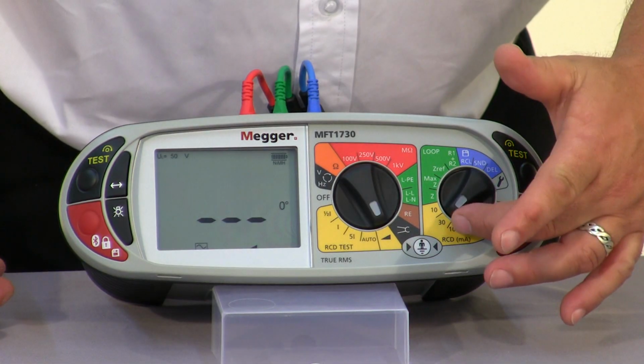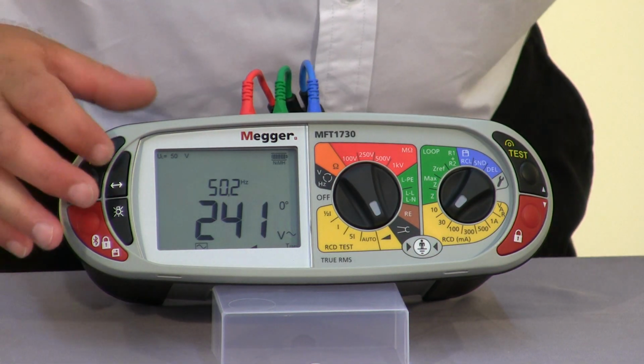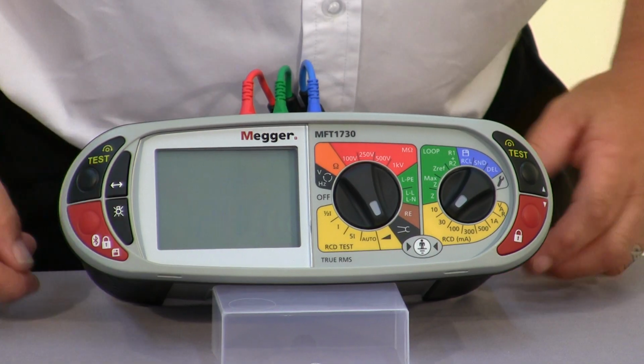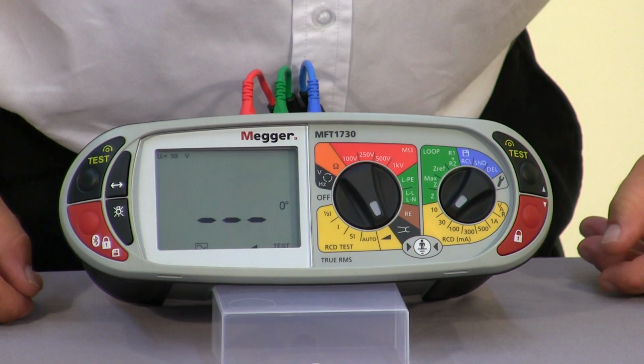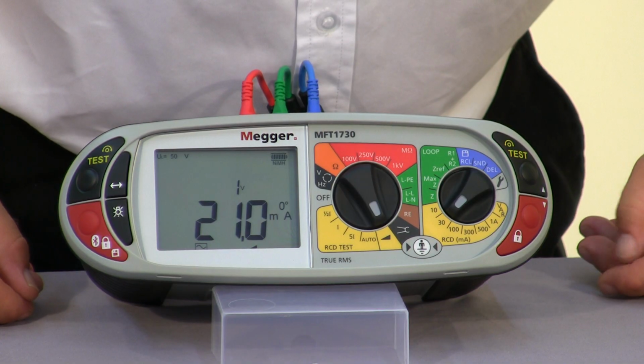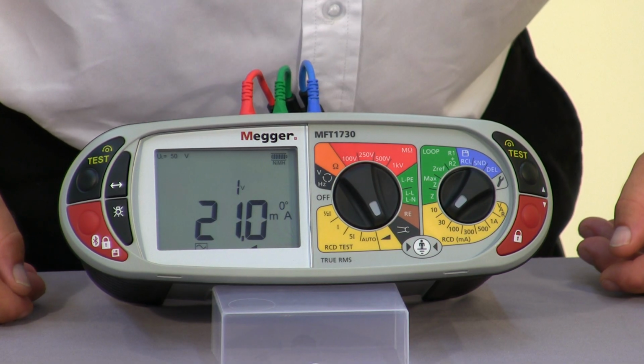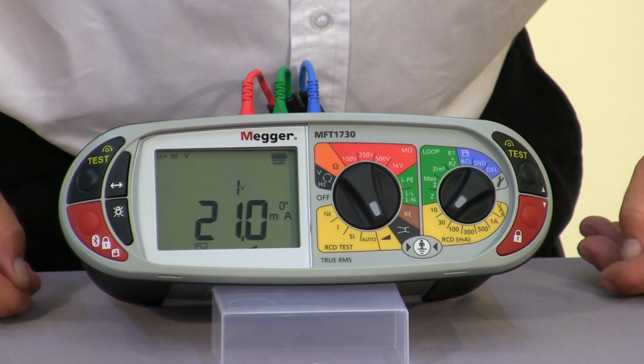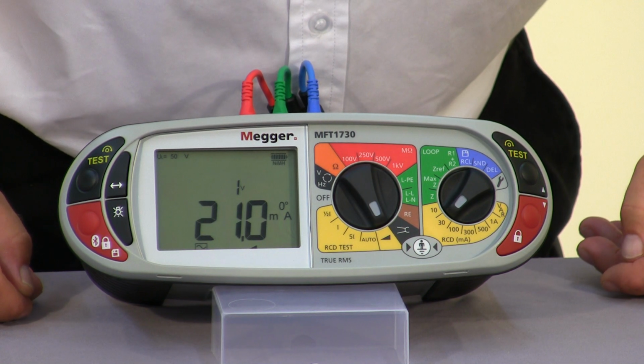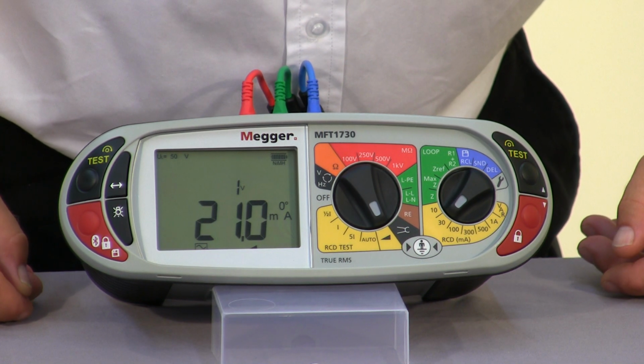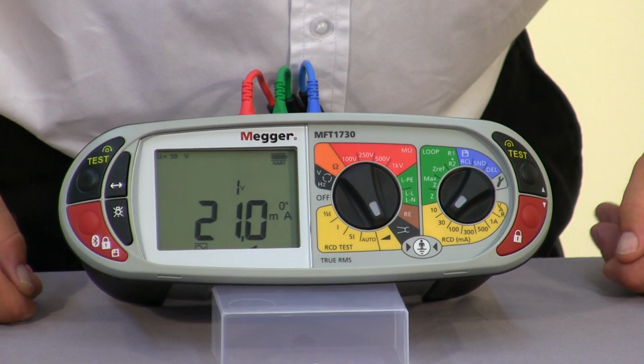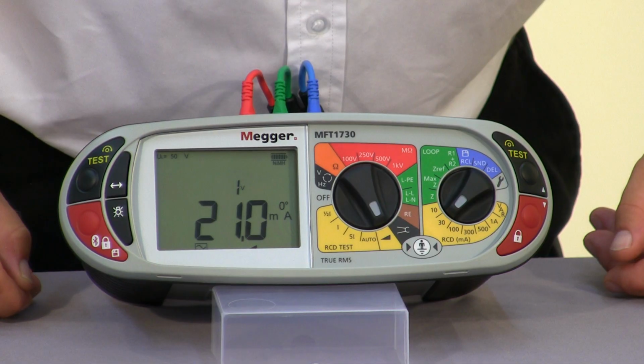The ramp test, again, with a standard 30 milliamp. We initiate the test. It will actually start at half the rated current of the RCD, and by ramping it up slowly indicate at exactly what value that RCD is operating. So in this instance, we can see that the RCD has actually tripped at 21 milliamps.